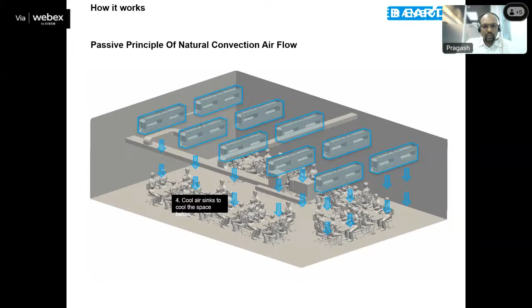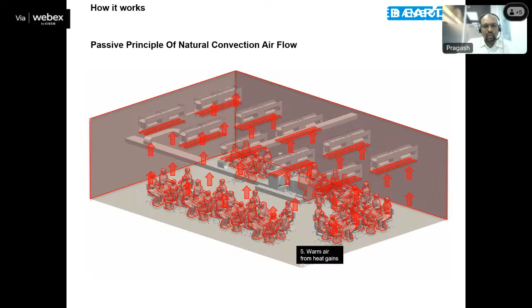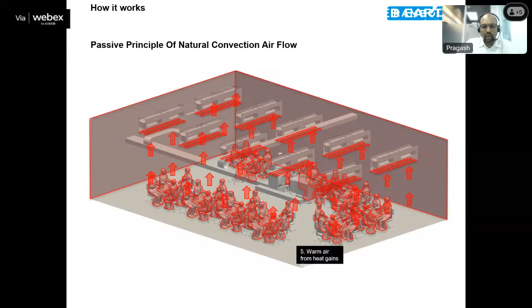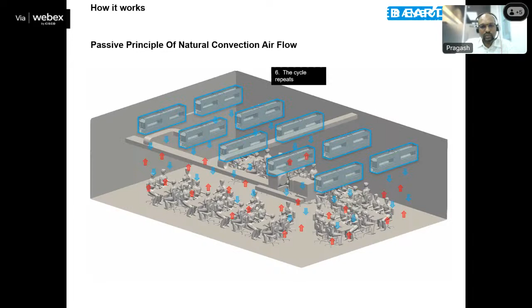Then the heat generated from the occupied zone and the lighting warms the air, and it circulates back to the ceiling level, and the cycle happens again. That hot air is cooled by the chilled water coil at the ceiling, and the cool air is directed down through the down duct built into the PDC system. So this cycle repeats. How do we achieve air circulation without any fan? This helps us achieve the net zero energy target and reduce the air circulation energy consumption.